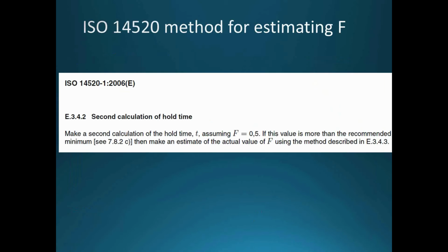Now, just touching on ISO momentarily, there's a mistake in ISO that was not in the 2000 version, but is in the 2006 version, and it was almost going into the next version, and I managed to catch it at the last minute, I believe. This value here must be assumed to be 0.15, not 0.5. So this is actually 0.5 in the standard, and it really is a mistake. It should be 0.15. If it's 0.5, the whole section makes no sense whatsoever. So the procedure would be that you would enter 0.15 as the leakage split.